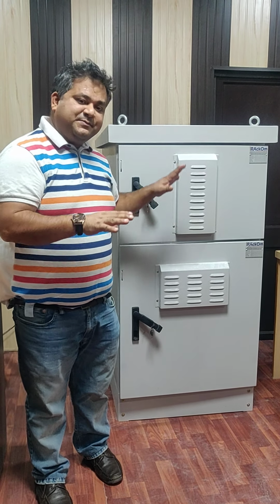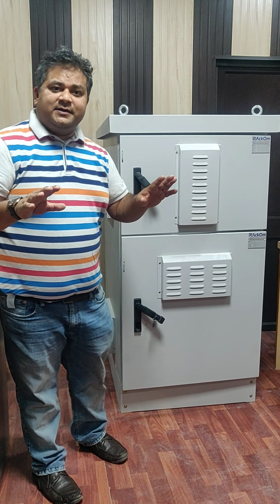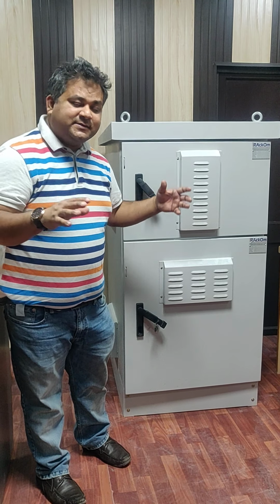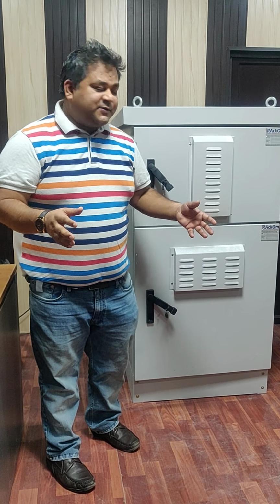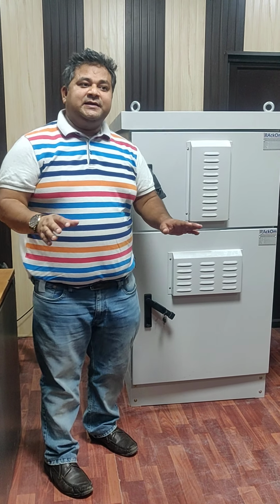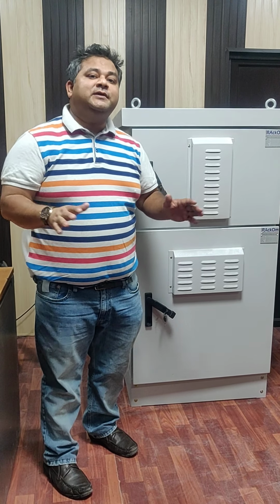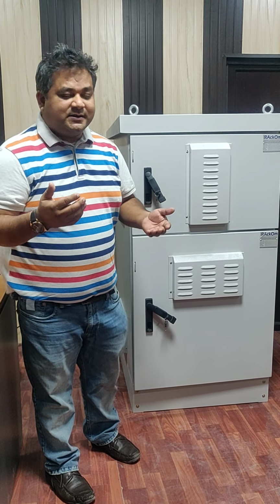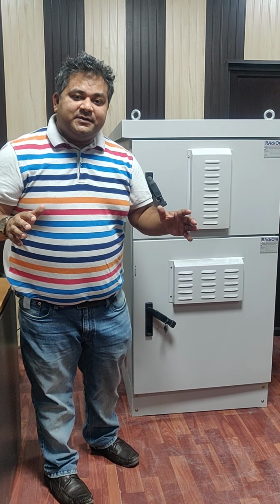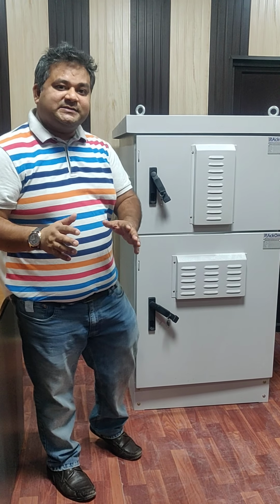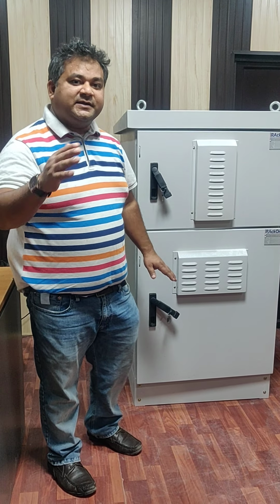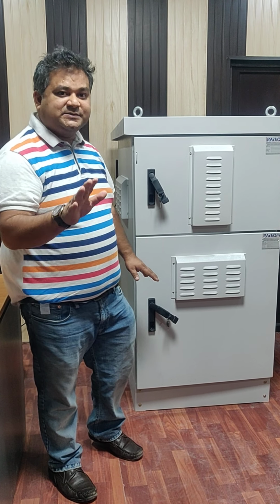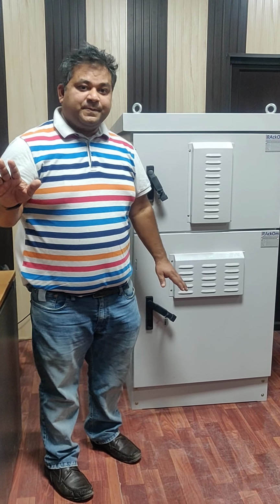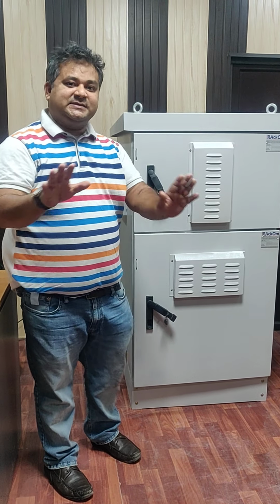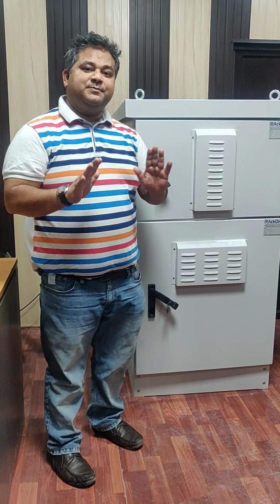Let me describe IP65. IP55 basically means water should not enter the cabinet from any angle, which is why we provide louvers, especially to keep rain water out. The first digit is for solids - dust ingress is permissible but only in a limited amount. In IP65, it's completely dust proof, but the water testing is the same. IP66 is completely closed - there should be no water ingress and no dust ingress at all. It's a completely sealed box.